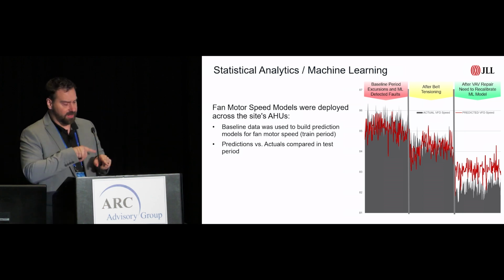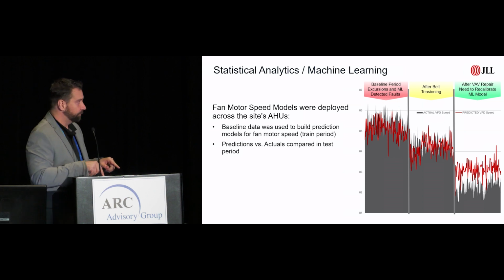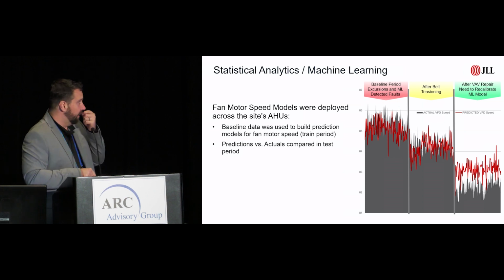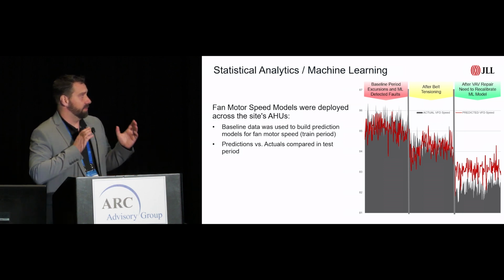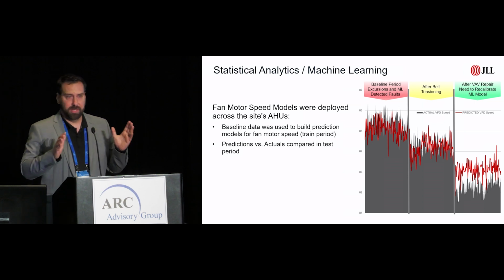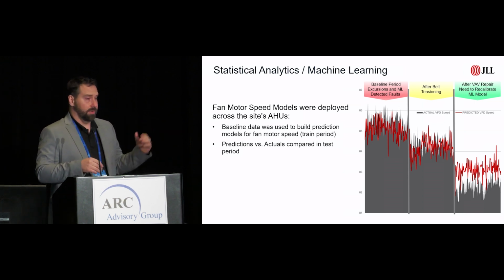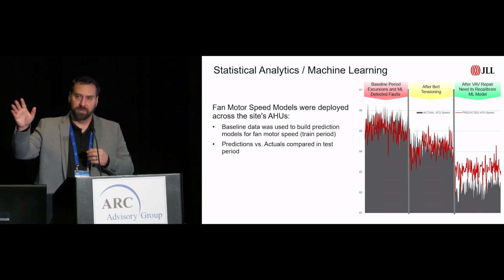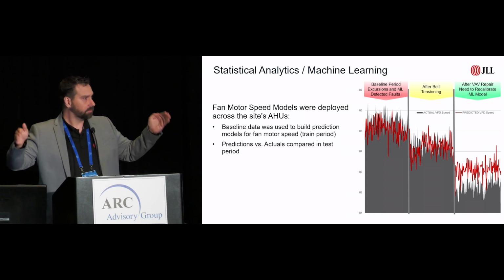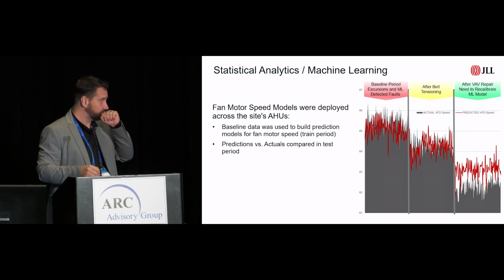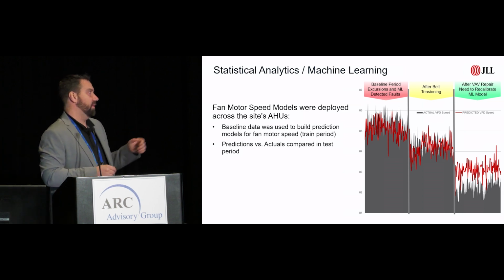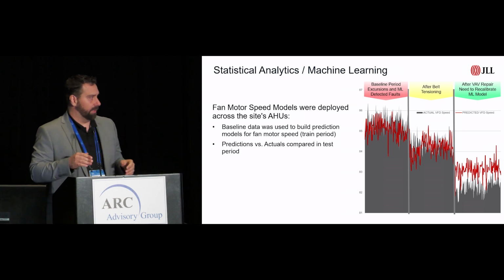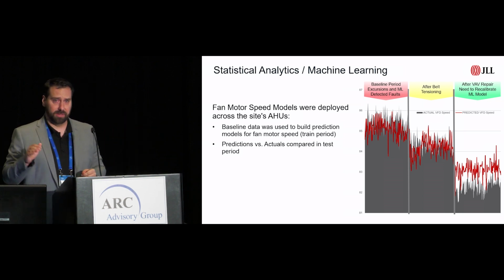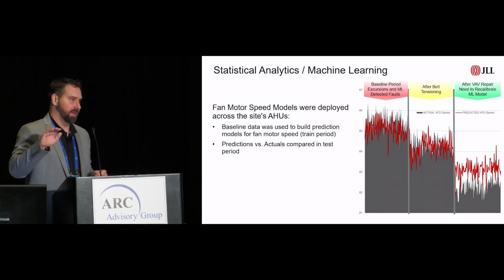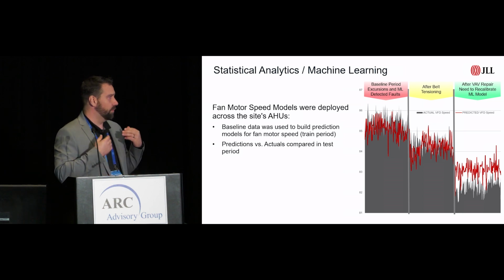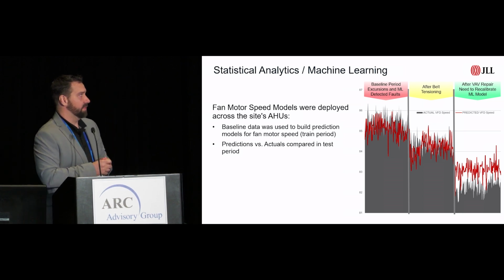And the system began to notice and identify issues around the actual piece of equipment that was affecting that equipment's performance. In this particular case on the screen, there's a device known as a VAV, a variable air volume unit. It's essentially a fancy damper. So imagine that this air unit is pumping air through a distribution system, and at every point of use, there's one of these little damper units opening and closing as required to maintain the system. There were a few of these VAVs indicating on the screen their position. However, in reality, that was not the case. We could see that the airflow was not matching what the percentage was supposed to be on the VAV. So we went out there, and lo and behold, there were about 5 or 6 of these that needed to be recalibrated.